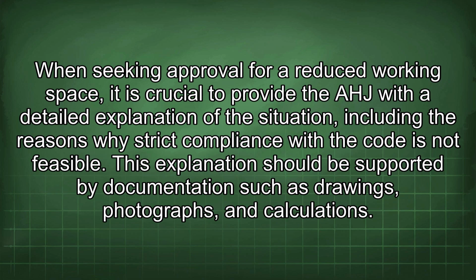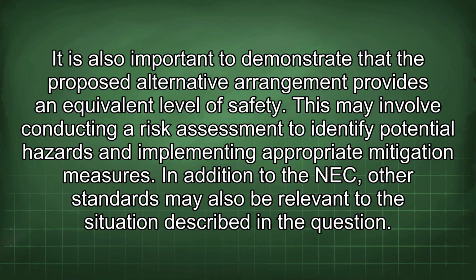When seeking approval for a reduced working space, it is crucial to provide the AHJ with a detailed explanation of the situation, including the reasons why strict compliance with the code is not feasible. This explanation should be supported by documentation such as drawings, photographs, and calculations. It is also important to demonstrate that the proposed alternative arrangement provides an equivalent level of safety. This may involve conducting a risk assessment to identify potential hazards and implementing appropriate mitigation measures.